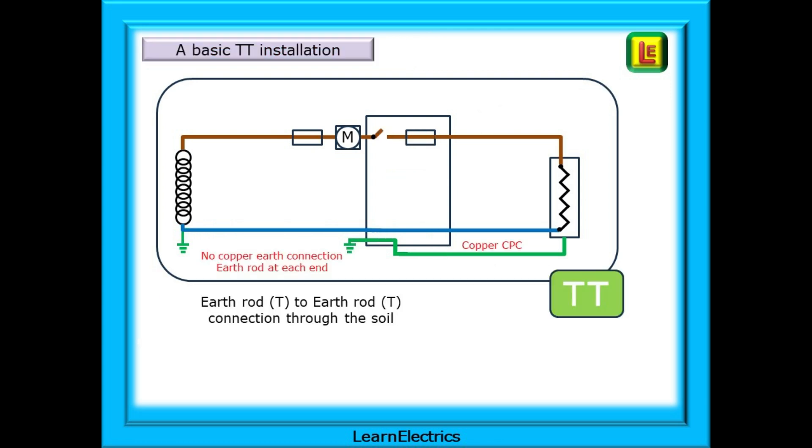And this is a basic TT system. T for terra or earth. TT stands for terra terra or earth rod T to earth rod T, with the electrical connection between the two being made through the soil. There is no copper connection between the earth at the supply transformer and the earth at the property and this has a big impact on our test results.